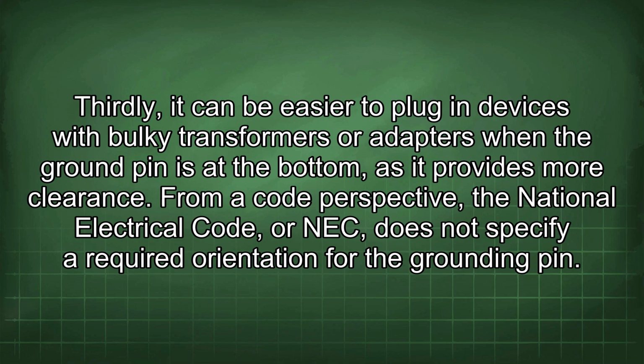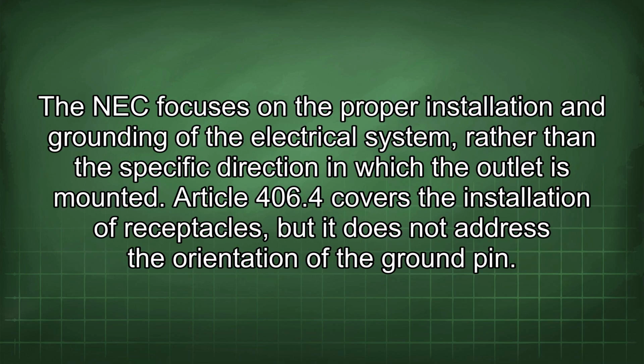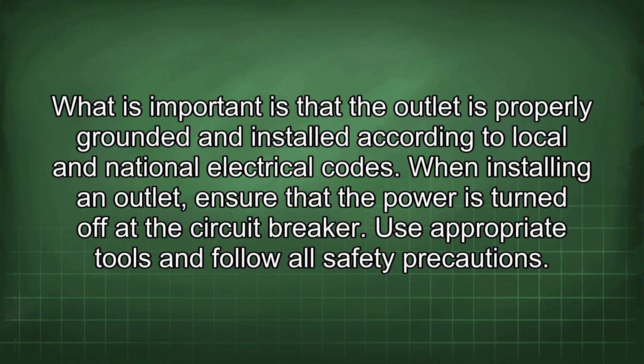From a code perspective, the National Electrical Code, or NEC, does not specify a required orientation for the grounding pin. The NEC focuses on proper installation and grounding of the electrical system rather than a specific direction for mounting the outlet. Article 406.4 covers the installation of receptacles but does not address ground pin orientation. What matters is that the outlet is properly grounded and installed according to local and national electrical codes.